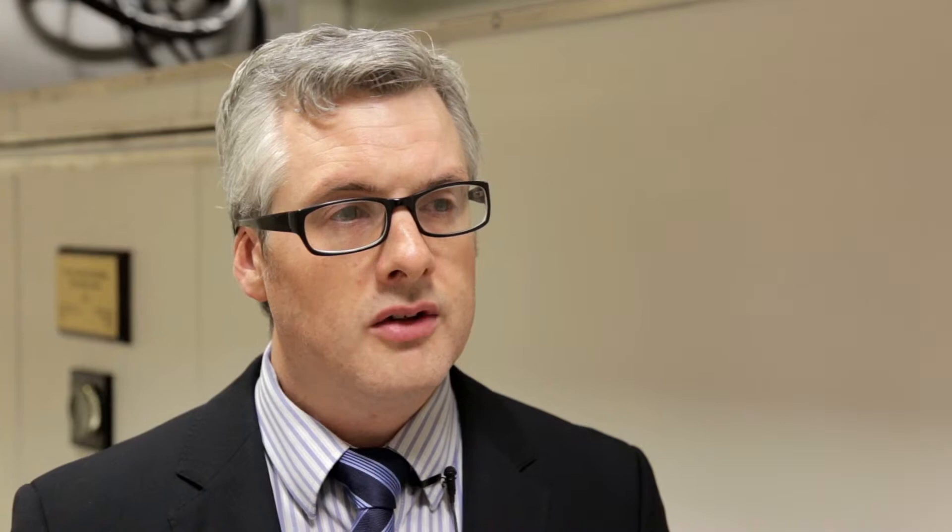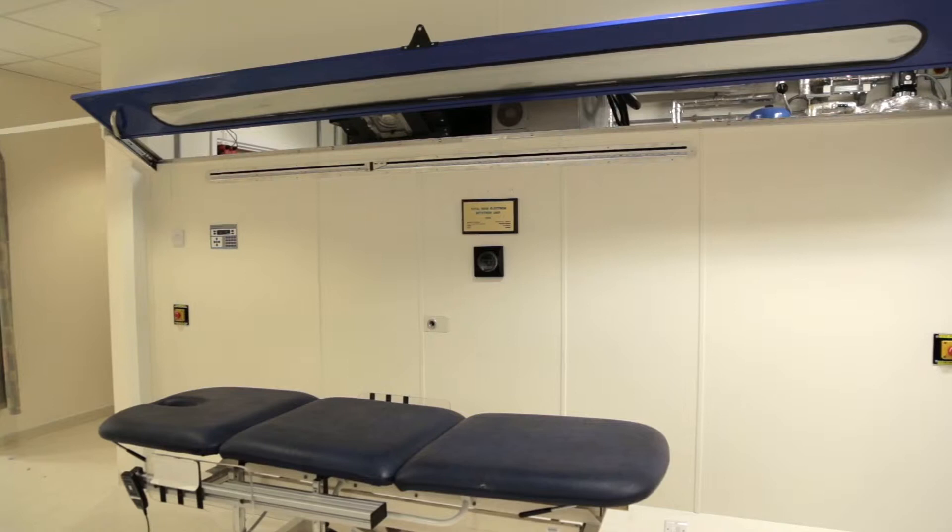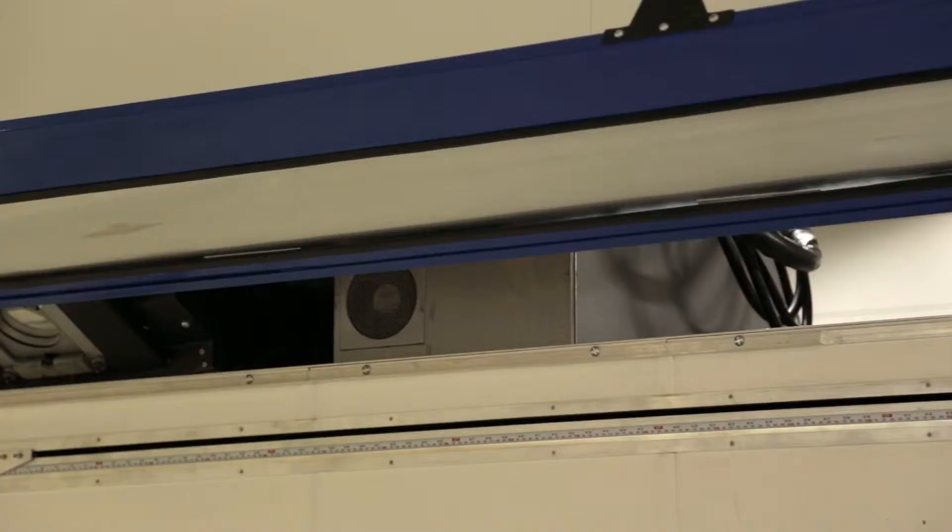The idea is we're trying to cover the patient with a uniform dose of electron beams. The specific advantage of the Betatron unit is that the compact Betatron unit can be translated across the patient, giving a very uniform dose distribution from head to toe. We achieve this by mounting the compact Betatron on the gantry and controlling the dose by varying the speed.